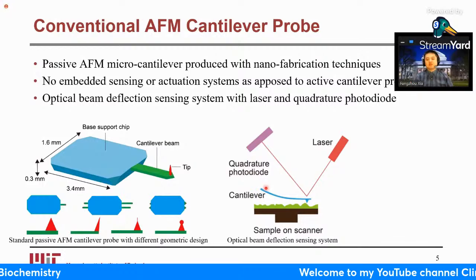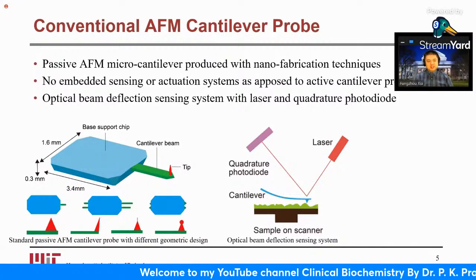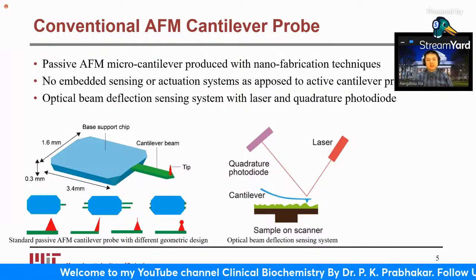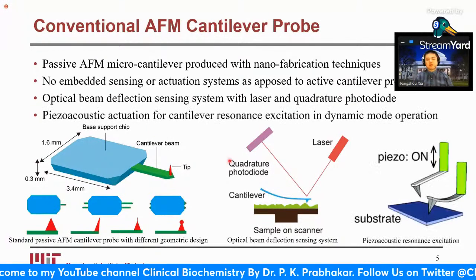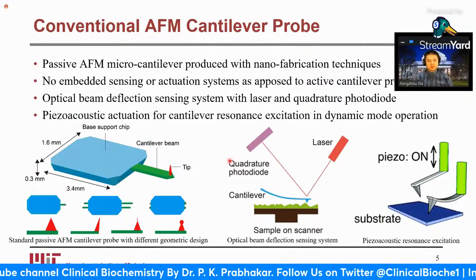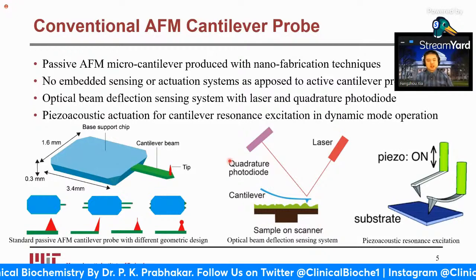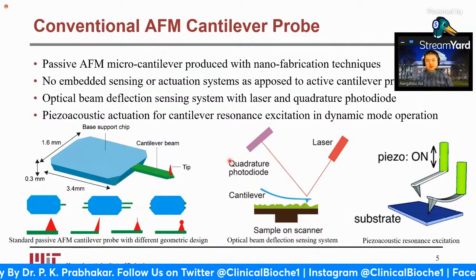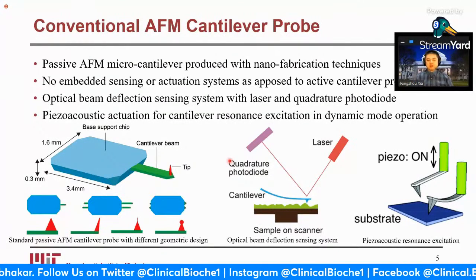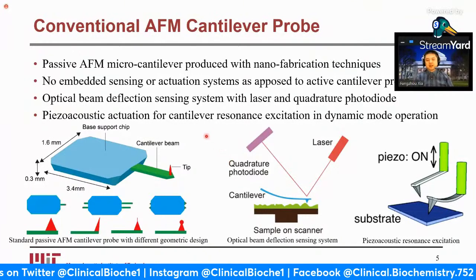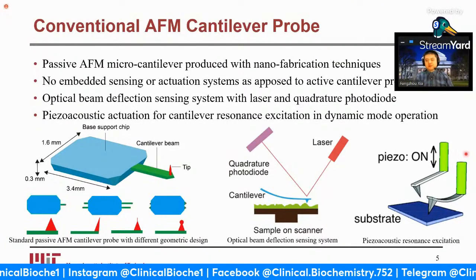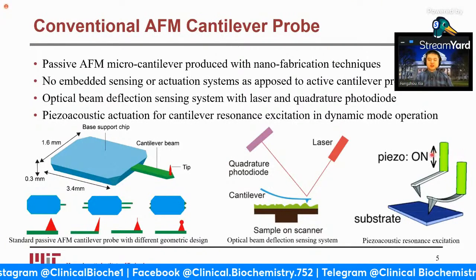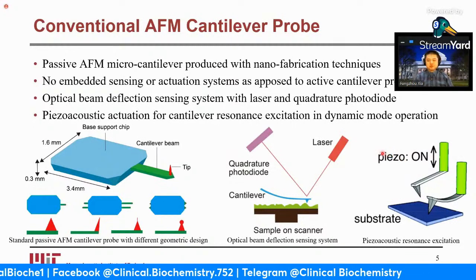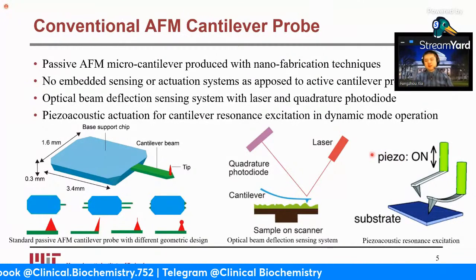So later you can use it for this measurement of the deflection. Other than sensing, for certain operations, especially in dynamic modes where you need to excite the resonance of the cantilever, piezoacoustic actuation is typically used. So you have a piezo actuator at the base or the holder of the probe, and then you acoustically excite the vibration by driving a sinusoidal wave to the piezo actuator at the resonance frequency of the cantilever, which sometimes needs to be identified during the experiment before you start the imaging.